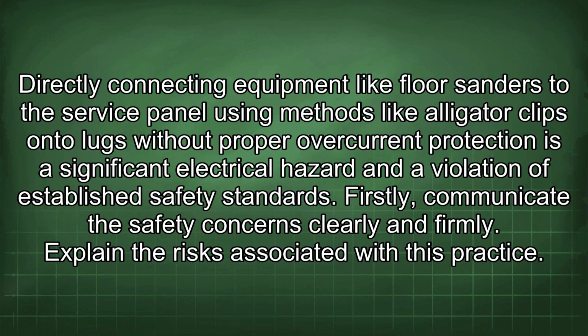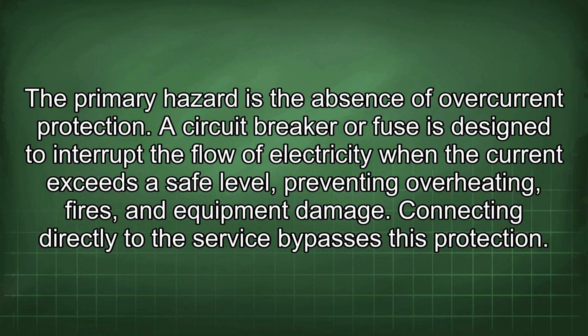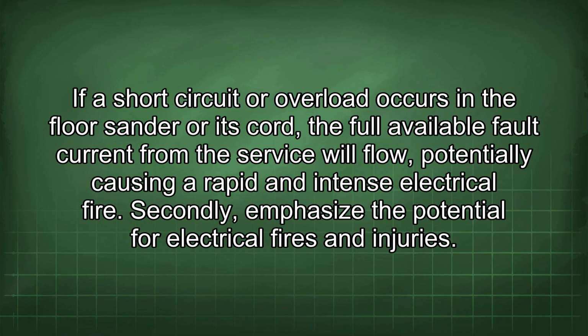Firstly, communicate the safety concerns clearly and firmly. Explain the risks associated with this practice. The primary hazard is the absence of overcurrent protection. A circuit breaker or fuse is designed to interrupt the flow of electricity when the current exceeds a safe level, preventing overheating, fires, and equipment damage. Connecting directly to the service bypasses this protection. If a short circuit or overload occurs in the floor sander or cord, the full available fault current from the service will flow, potentially causing a rapid and intense electrical fire.